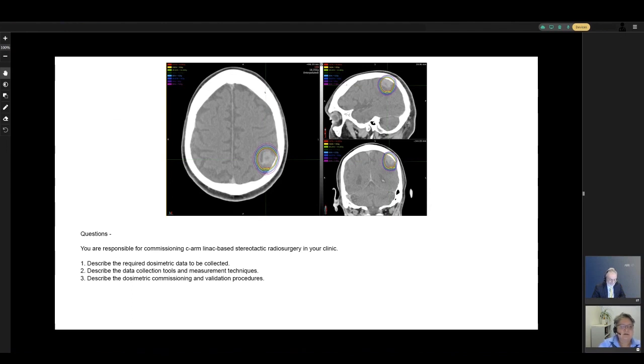You also need to pay close attention to your MLC. So most likely you're going to have a high definition MLC, and you need to know things like dosimetric leaf gap, transmission, penumbra, tongue and groove effect. So all of that needs to be well modeled in your treatment planning system. And the tools you measure for the PDD and profiles and output factor, it's really very much the same tools you would use to calibrate a LINAC. So you need a water tank, your ionization chambers, diodes, whatever measurement device you're using.